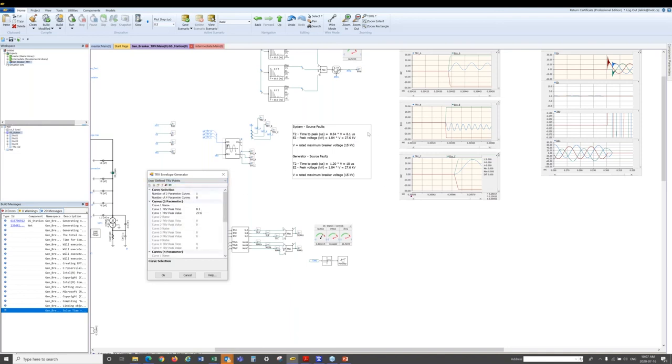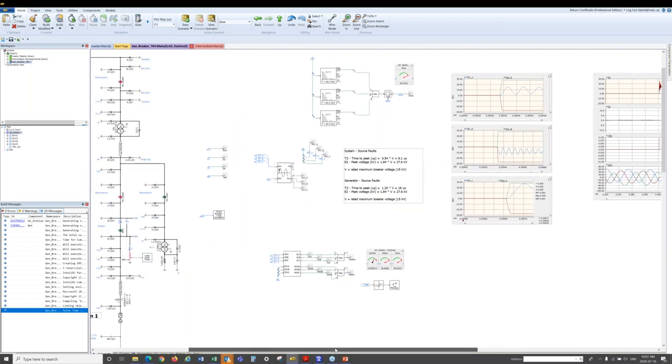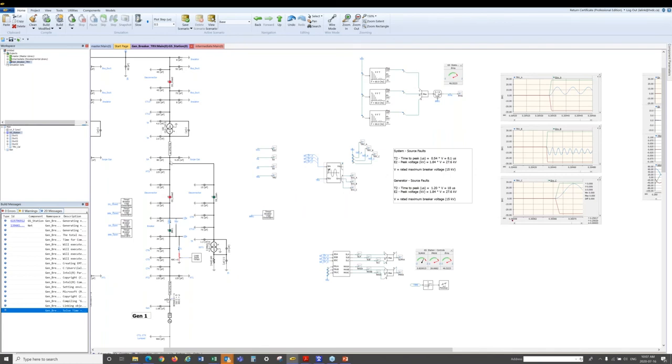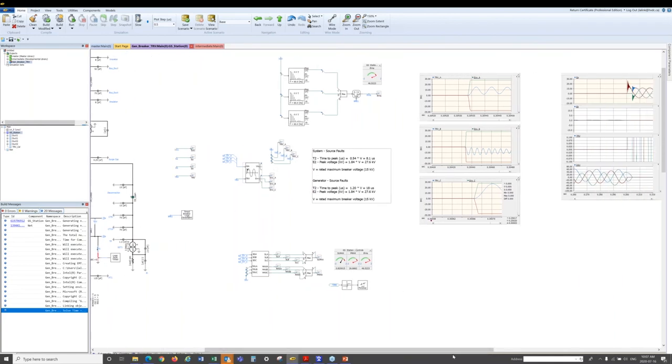We can share these example cases with you and you can have a further look. In this particular case, you have a single curve, there's no fault duty for the generator breakers. So in this particular case, we don't have a violation. Actually, this is because of some large stray capacitances. They contribute towards a low frequency, so therefore I don't see any violation here. But the main idea here is to demonstrate how to perform the simulation.